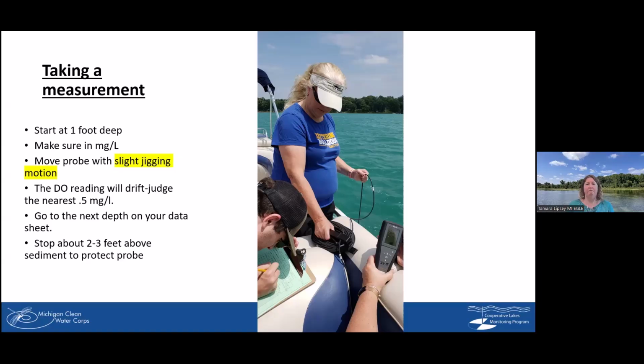And so what I mean on that is, when you're measuring dissolved oxygen and you're changing depths, it's going to take a few minutes for it to stabilize. So it might say 11.6 milligrams per liter, 11.2, 10.9, 10.5, 9.2, 8.4, 8.9, 9.0. So once it starts to get where the tenths number is just changing by 1 or 2, that's when you take that measurement. You don't have to wait for it to absolutely stop, but as long as you're within 0.5, that'll be fine.